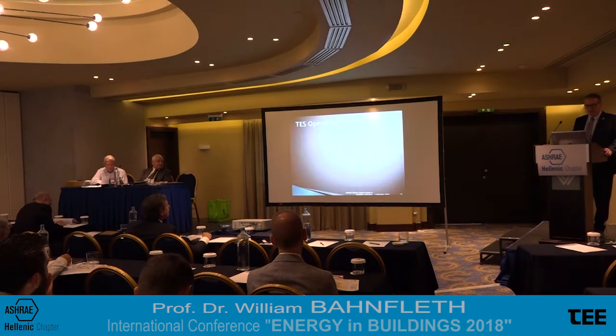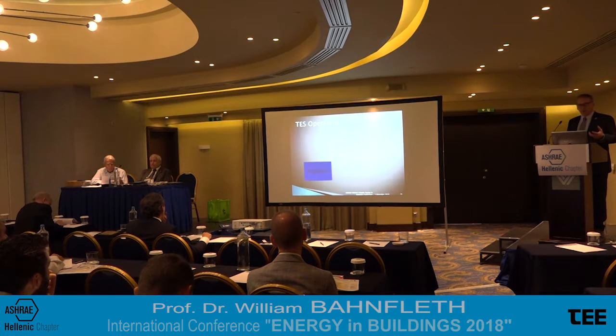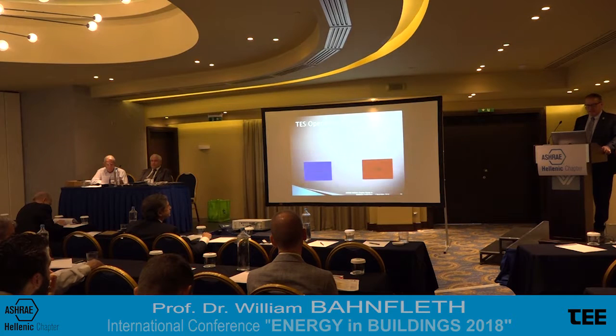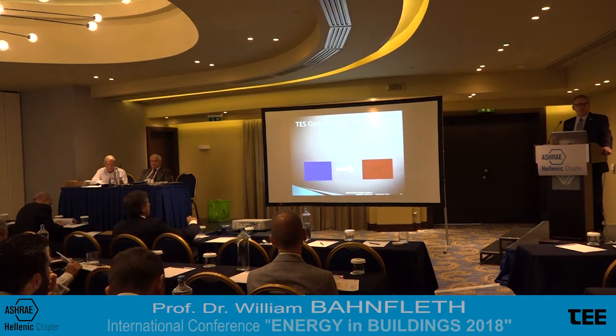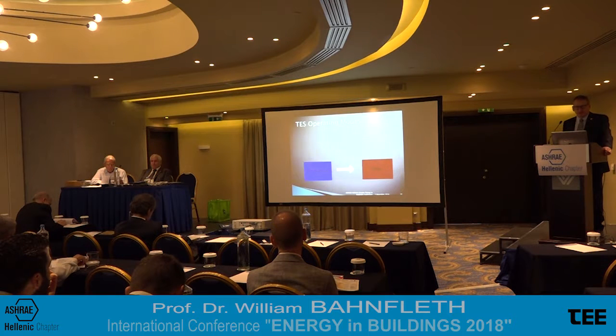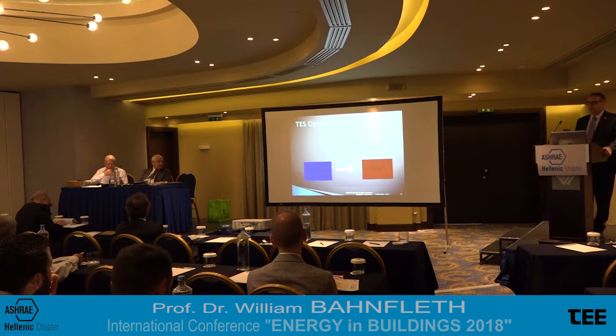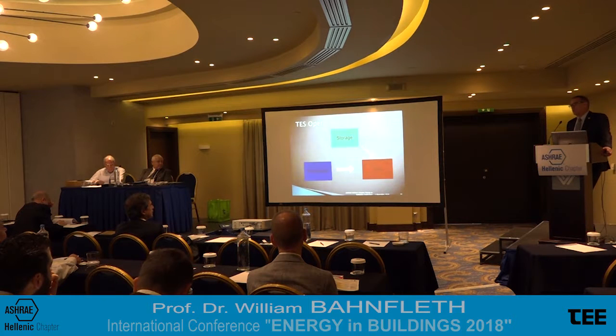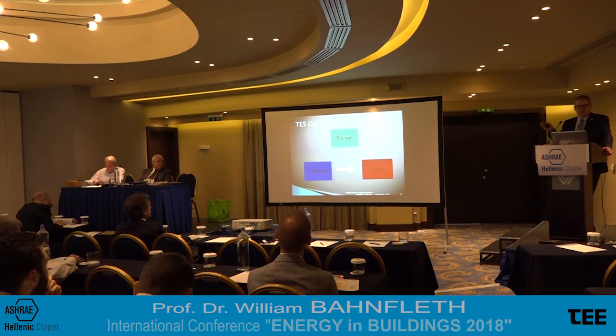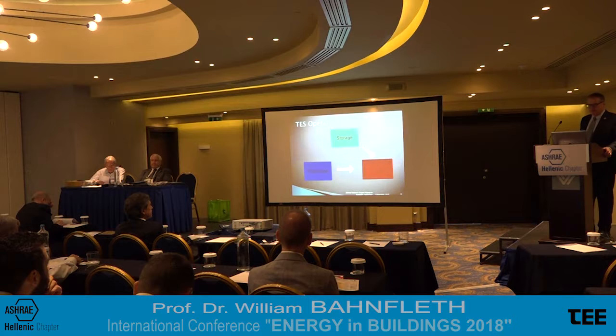So when we're doing thermal storage, we have to move around cooling capacity. It's illustrated here. We have a production unit, the plant that can produce cooling capacity, and it delivers it to the end users, wherever they might be, an air conditioning application for an office or a data center or some other process. This is the non-storage scenario, in which whatever the load is determines what the plant produces. When we add storage to the system, by taking stored cooling capacity out of it, we can now use an arbitrary combination of direct and discharge capacity to meet that load.